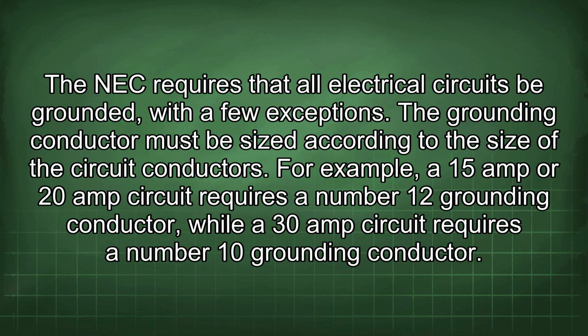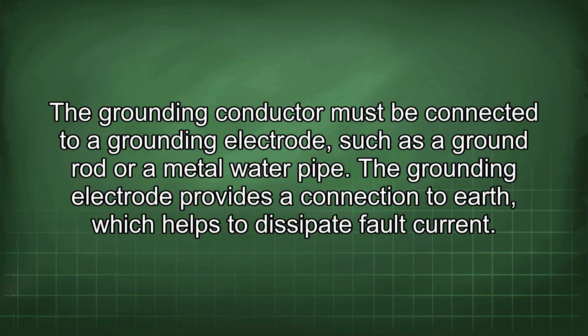The NEC requires that all electrical circuits be grounded, with a few exceptions. The grounding conductor must be sized according to the size of the circuit conductors. For example, a 15 amp or 20 amp circuit requires a number 12 grounding conductor, while a 30 amp circuit requires a number 10 grounding conductor. The grounding conductor must be connected to a grounding electrode, such as a ground rod or a metal water pipe. The grounding electrode provides a connection to earth, which helps to dissipate fault current.